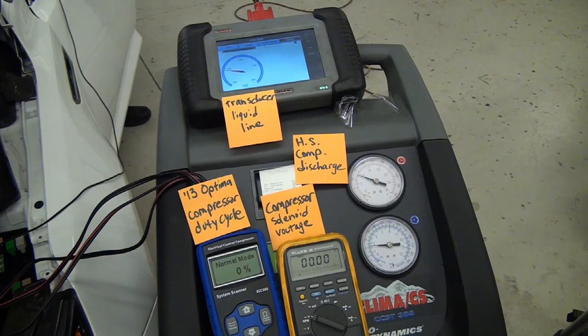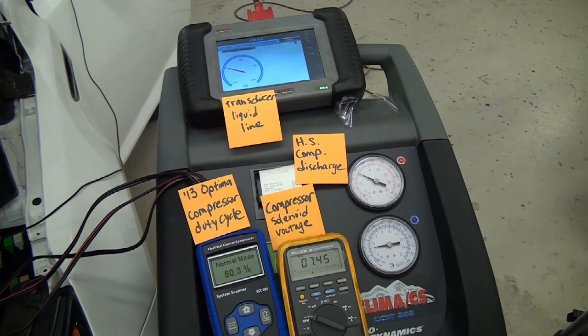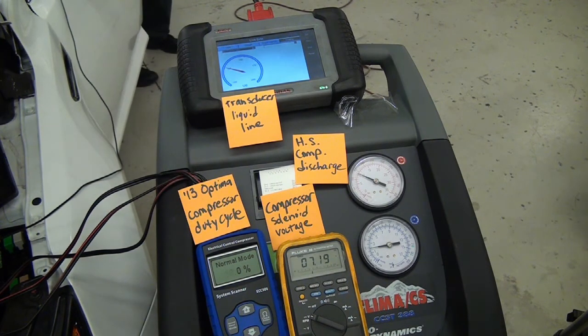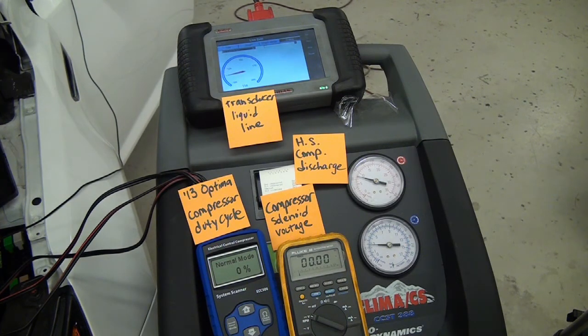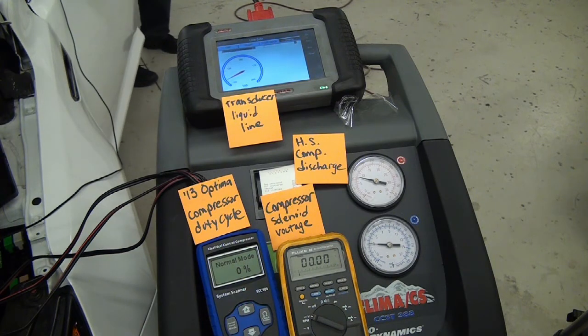So what appears to be happening is, as the heat load on the system is decreasing, during this time the PCM is actually turning off the signal to the compressor solenoid valve. You can hear a change in the tone in the engine and also see the Fluke meter and the duty cycle meter drop all the way down to 0. But since there still is a call for cooling, the PCM has to turn the compressor back on at some point to keep the evaporator temperature at the set level.